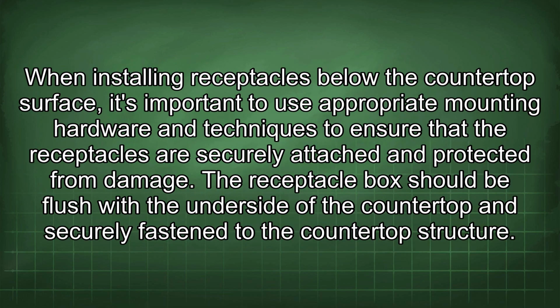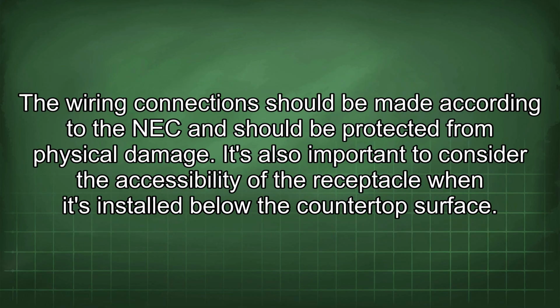When installing receptacles below the countertop surface, it's important to use appropriate mounting hardware and techniques to ensure that the receptacles are securely attached and protected from damage. The receptacle box should be flush with the underside of the countertop and securely fastened to the countertop structure. The wiring connections should be made according to the NEC and should be protected from physical damage.